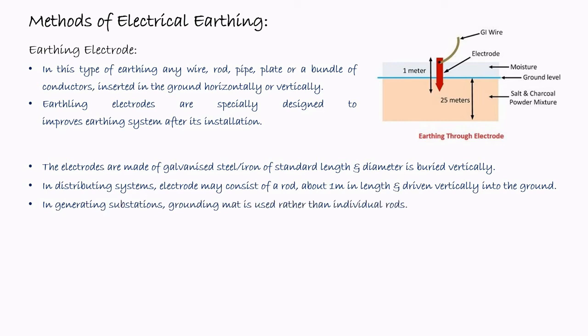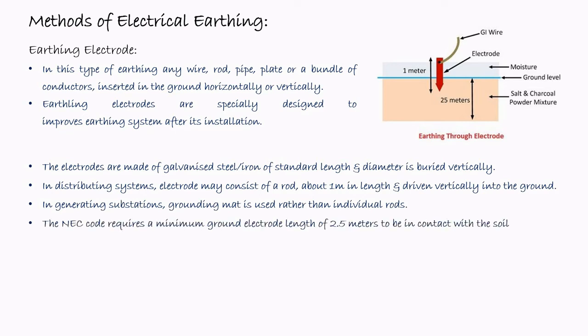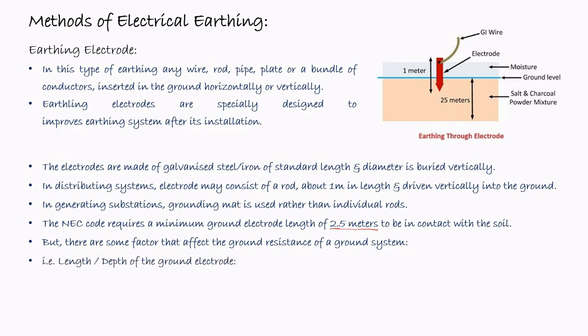In generating substations, a grounding mat is used rather than individual rods. The National Electrical Code requires a minimum ground electrode length of 2.5 meters to be in contact with the soil. So this is the standard according to the National Electrical Code. That is, the length of the electrode should be around 2.5 meters. But there are some factors that affect the ground resistance of a ground system, such as the length versus depth of the ground electrode and so on. Now, if the length is doubled, it will reduce the ground resistance by up to 40%. Therefore, the length should be as high as possible, and as per the standard it should be around 2.5 meters.